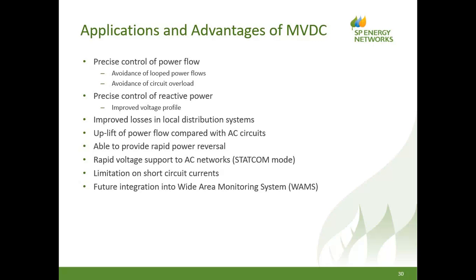We can also reverse power very, very quickly. I suspect we can reverse power too quickly for the AC systems to accommodate it, so we would have to slow that down. But power can be reversed in milliseconds through a DC link. It's the nature of the voltage source converter that to reverse power, we don't have to change polarity of the cables. We can keep the polarity as it was and merely change the current direction. So this can be done very quickly.